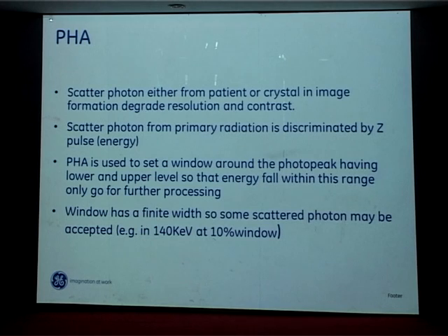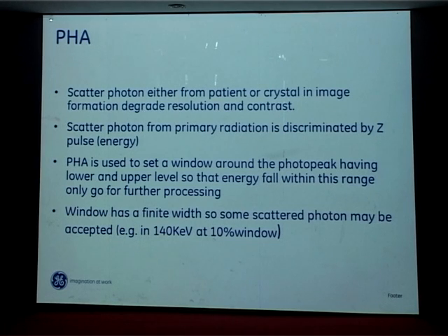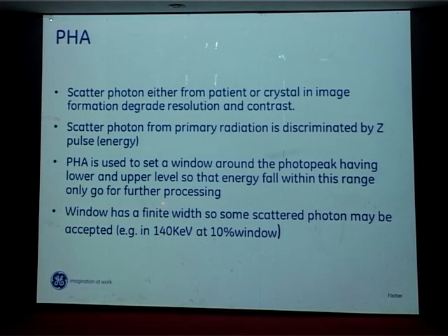Scatter from photons degrades image resolution and contrast. Scatter from primary radiation is discriminated by its pulse energy. The PHA sets a window around the photopeak — the main gamma energy that the particular radioisotope emits — with lower and upper levels so that only energy falling within this range goes for further processing. For technetium, which is commonly used in gamma camera studies, the peak is 140 keV. We set a 10% window, so from 130 to 150 keV, only energy within that range is accepted for image formation.